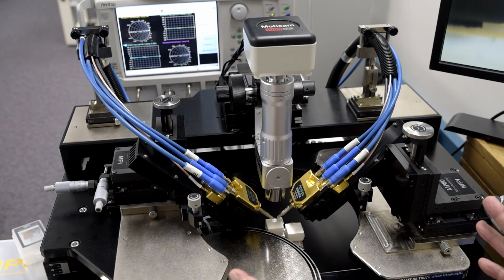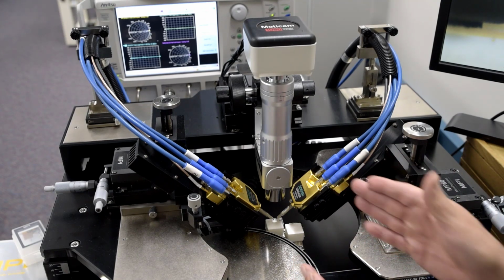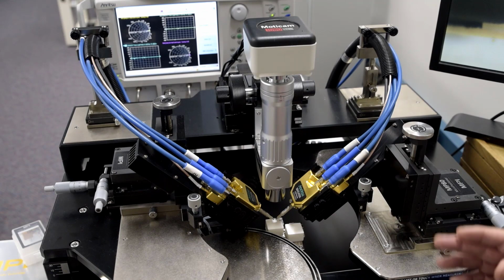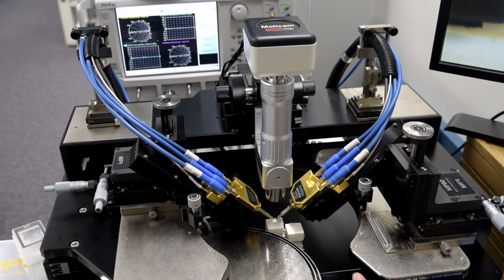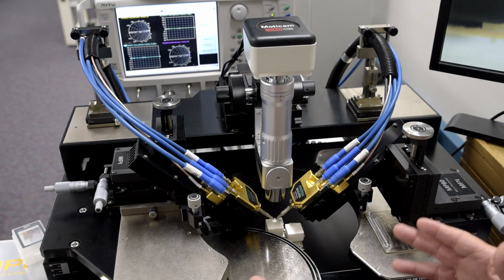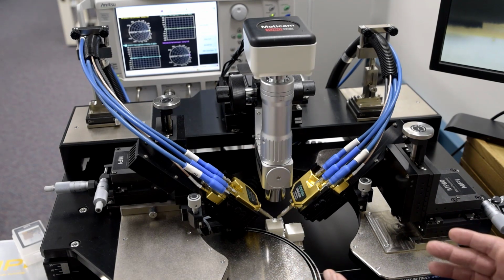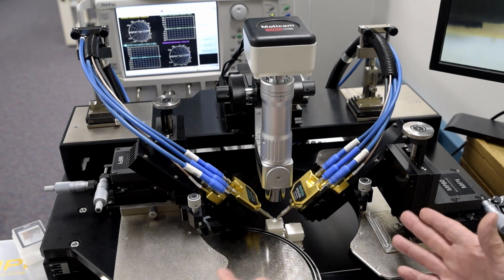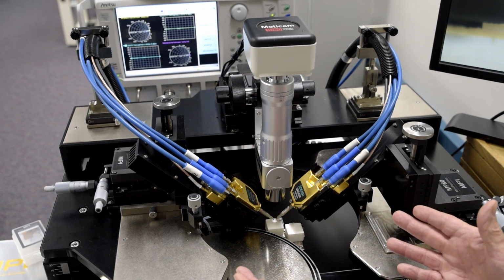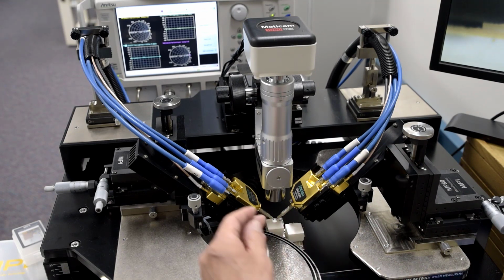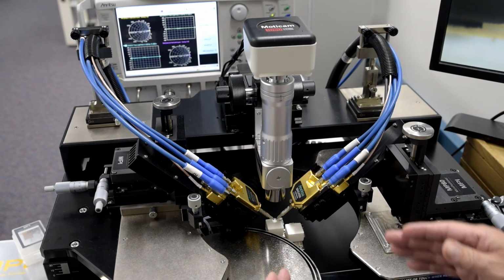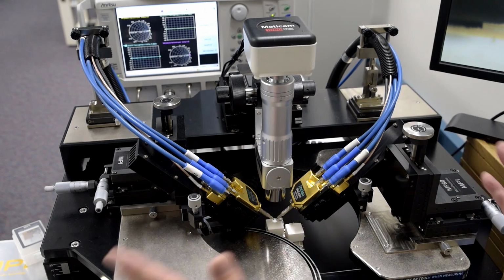Now, many of these points that we'll be discussing will apply to all the broadband systems available for VectorStar, which uses the NLTL, the nonlinear transmission line modules, to upconvert the frequencies to the millimeter wave bands. And so for the case of the different ME7838 systems, we have a 110 gigahertz system, a 125 gigahertz system, a 145 gigahertz system, and then the 220. So by changing these modules, you can determine the upper frequency range of the probing system.